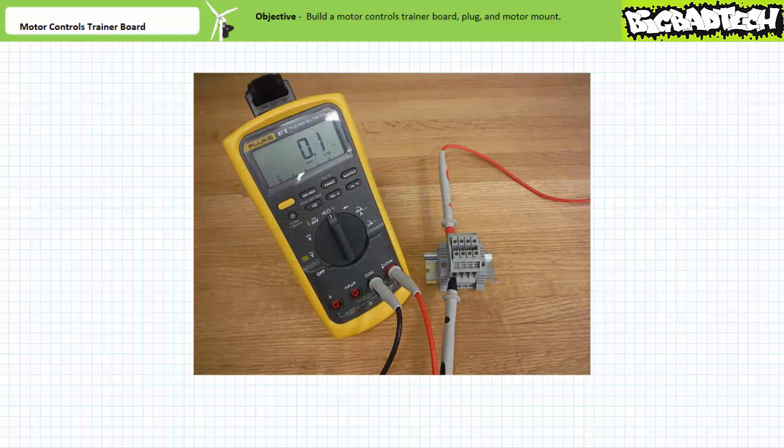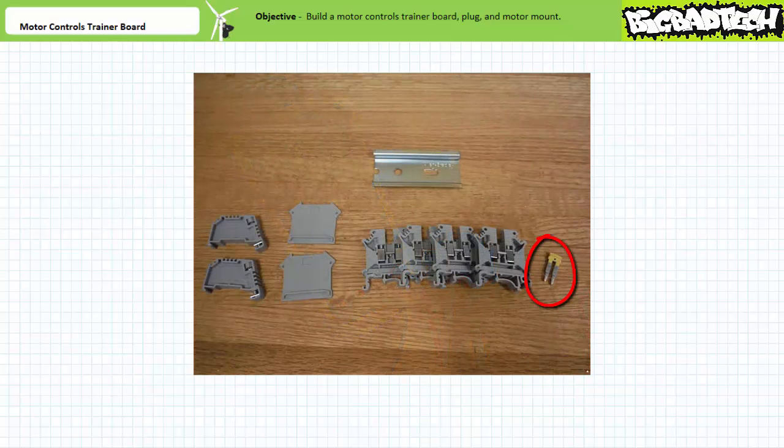An ohmmeter indicates connection across an individual terminal block. However, an ohmmeter indicates there is no connection to the neighboring terminal block. Despite their close proximity, each terminal block is to be considered an isolated entity insulated from each other and the DIN rail. Note special fittings like jumpers can link side-by-side terminal blocks together, making it possible to pool connections without a lot of messy wires.